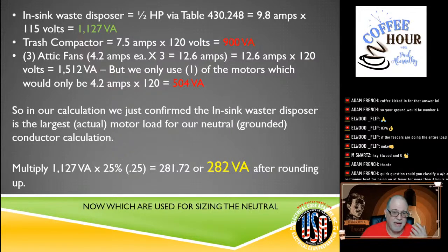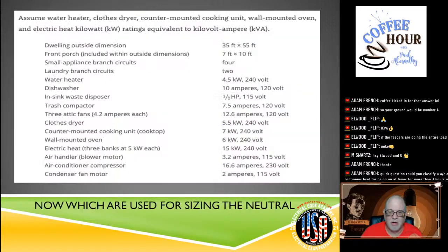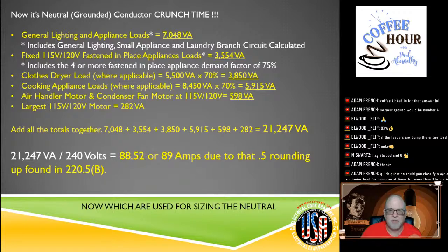It's 1,127 VA times 0.25. It is 281.72. Because of 220.5(B), we're going to round it up to 282. So that's our contribution. So we covered all the neutral loads. So let's add them up.